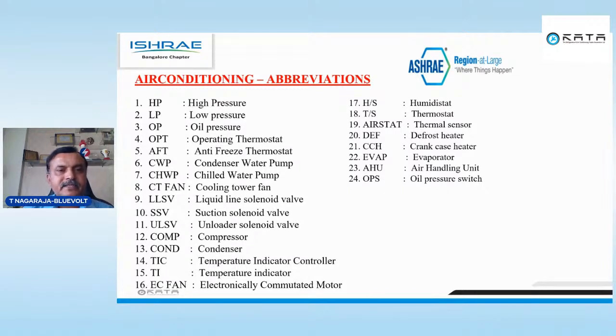Nowadays, with our PLC, only one sensor will do both jobs. OPT is set at a certain level, I think 4 to 6 degrees. Once it crosses this level going below, it will be considered as antifreeze. So below 4 degrees, or whatever the required set point is, our PLC or display will automatically show that it is crossing the dangerous zone.